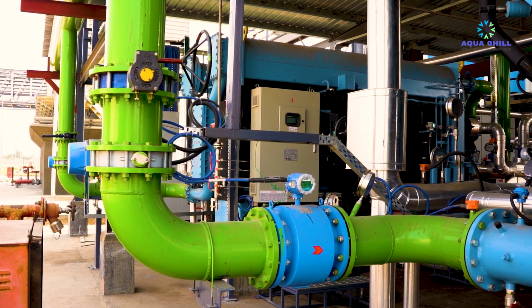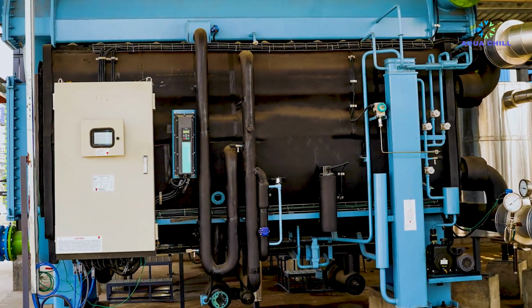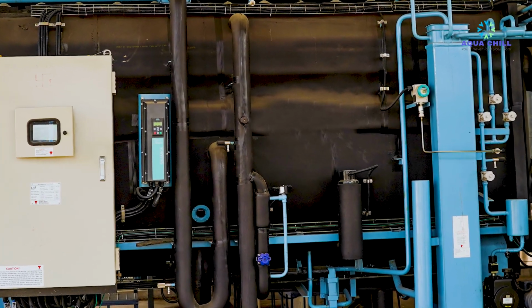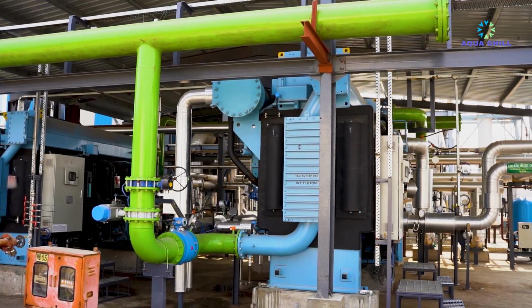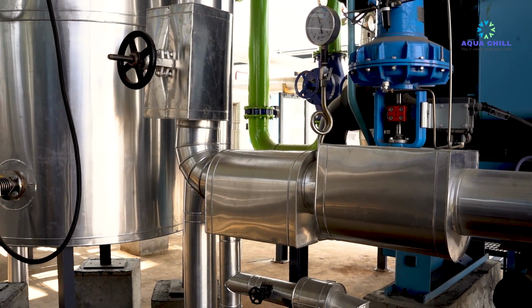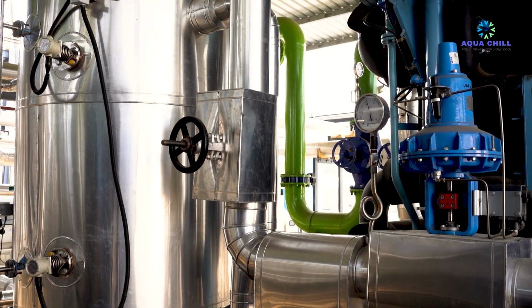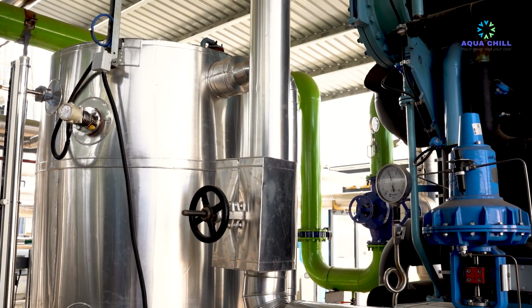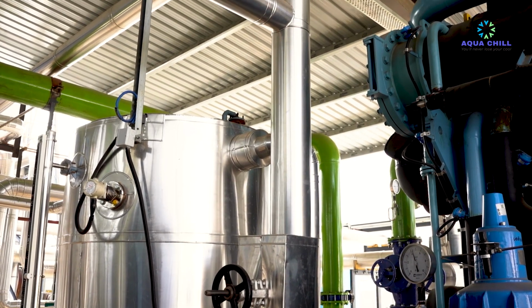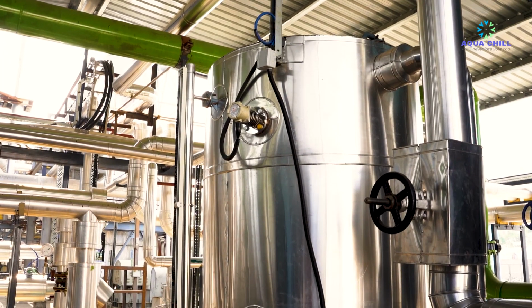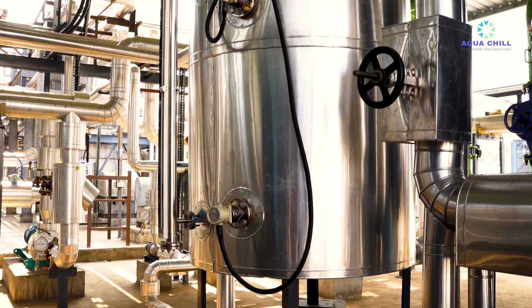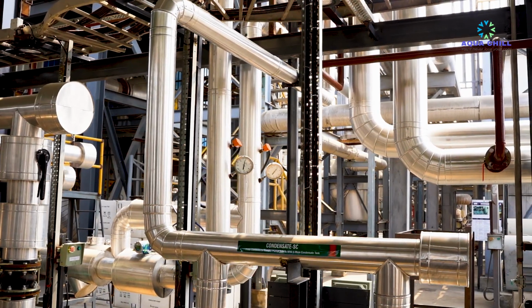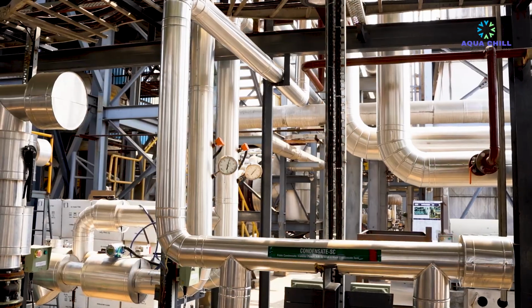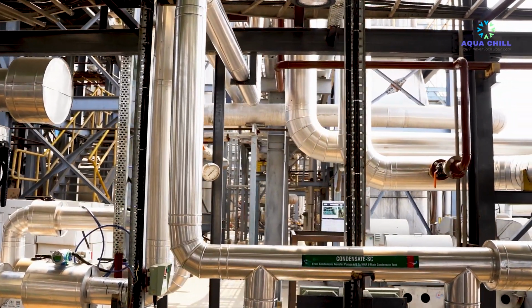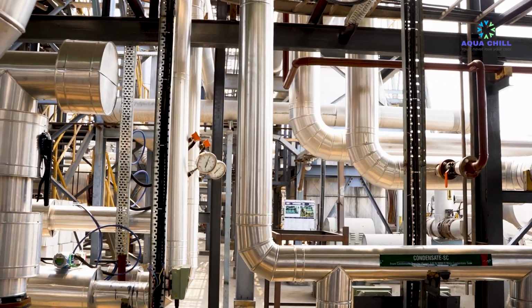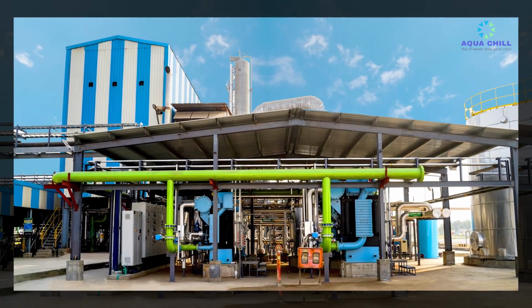This cooling was to be achieved by using absorption chillers, as low-cost steam was available from the recently implemented gas recovery project. There were three critical challenges in this implementation. One was to achieve the thermal performance of cooling the ambient air to the ISO condition irrespective of season changes. This challenge was managed by selecting the cooling generation equipment and the cooling delivery equipment of appropriate sizes. It also involved selecting the right metallurgy for the ammonia environment which is present in this plant.